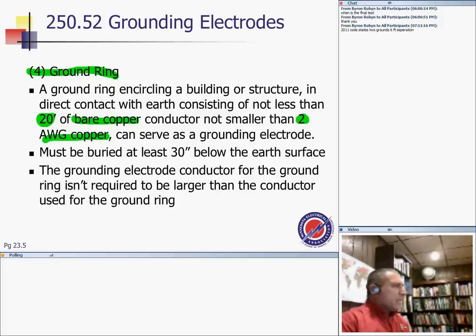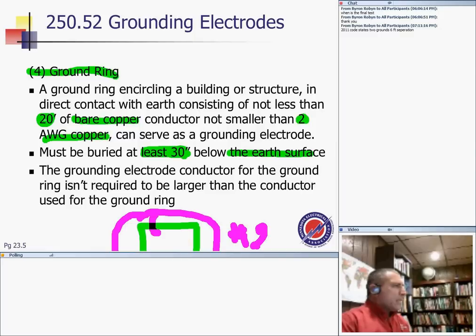Serving as the grounding electrode conductor, it has to be buried at least 30 inches below the surface. And for the ground, it's not required to be larger than the ring. Okay, so basically, here's your building. We did this a couple of times, guys. You have your building and you have a ring. You can go around your building with a ring, and you tie it and bring it to the building, and that will be number 2, and that will act around that building. That's the ground ring. Oops, that's the color to use. Okay, and it's buried at least 30 inches in direct contact, and you're good to go.